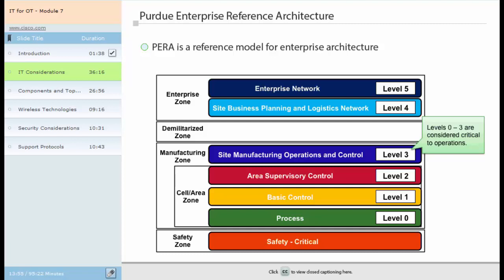Critical to cell area levels are the environmental conditions in which the network infrastructure operates. Important considerations when selecting network components include: extended temperature ranges, humidity tolerance, shock and vibration resistance, electromagnetic constraints and surge protection, immunity to noise, support of various power input options including AC or DC inputs, support for various media types such as fibre and copper, flexible port configurations, and mounting options.